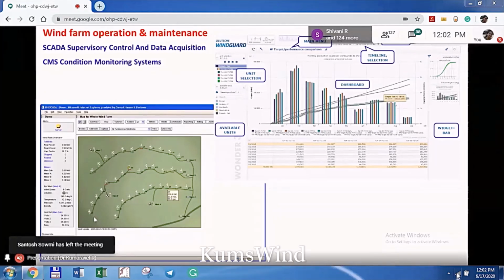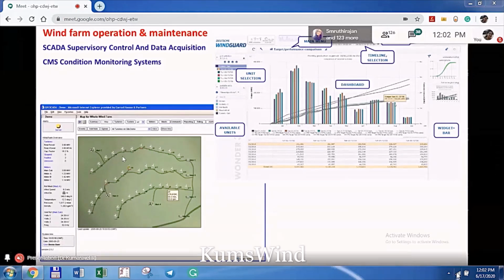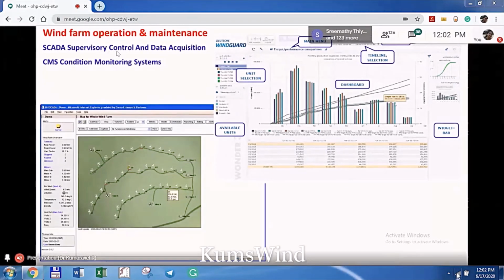So you need proper spacing, which is called micro siting of every wind turbine—you have to locate these turbines at a micro level. A wind farm of 50-60 turbines can spread across several square kilometers, so monitoring it requires a supervisory control and data acquisition (SCADA) system, also used for condition monitoring or health monitoring of wind farms. Every individual turbine has a controller, and all controllers can be connected to the internet, linked to one common computer or system where you can control, sit, and monitor everything from one place.